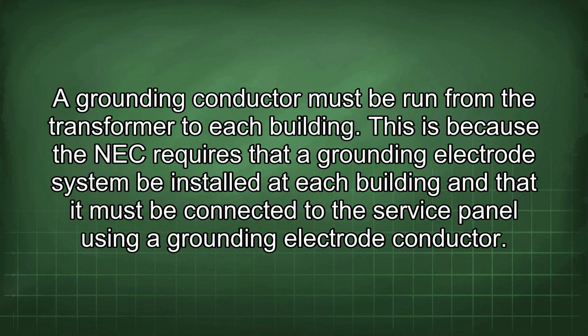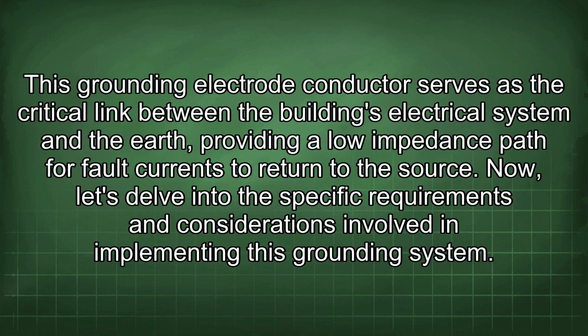This is because the NEC requires that a grounding electrode system be installed at each building and that it must be connected to the service panel using a grounding electrode conductor. This grounding electrode conductor serves as the critical link between the building's electrical system and the earth, providing a low impedance path for fault currents to return to the source. Now let's delve into the specific requirements and considerations involved in implementing this grounding system.